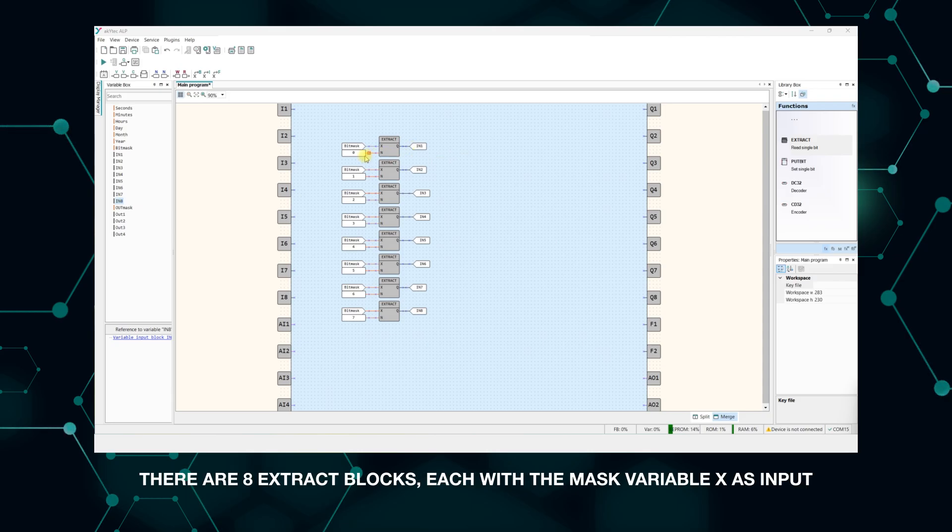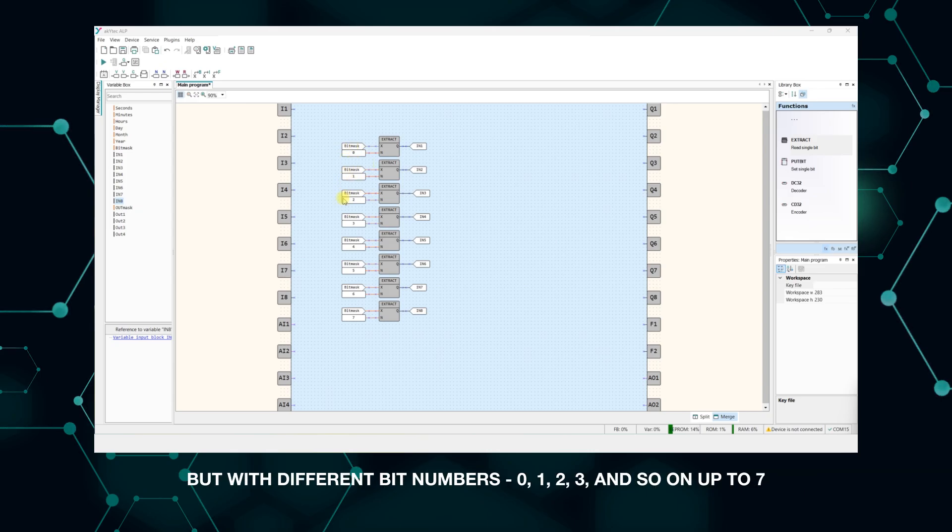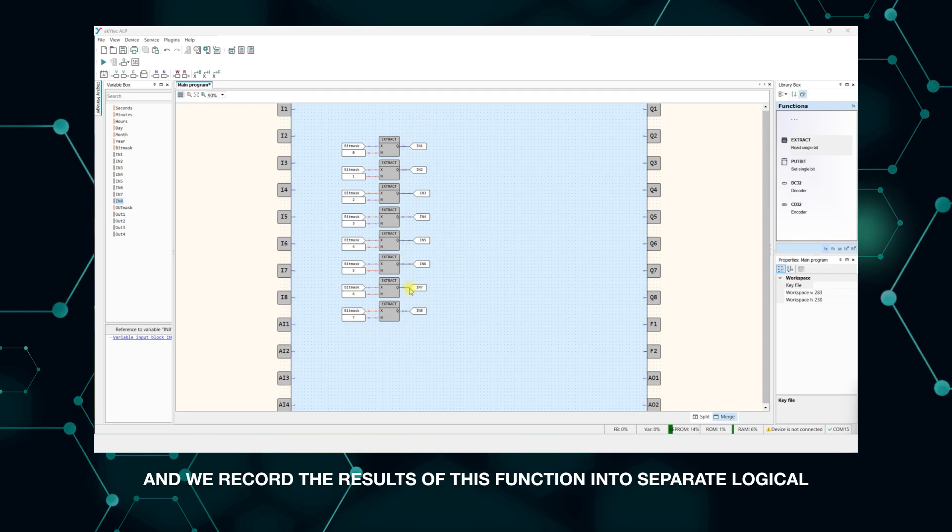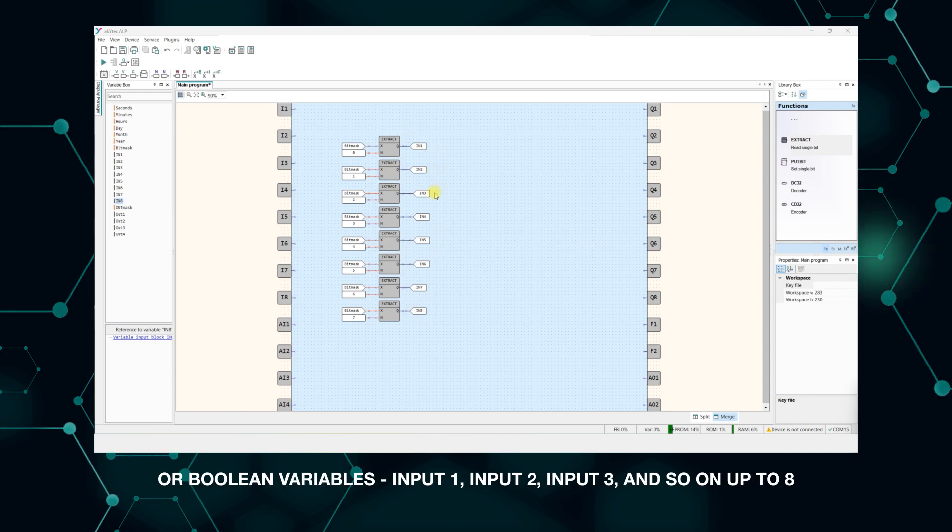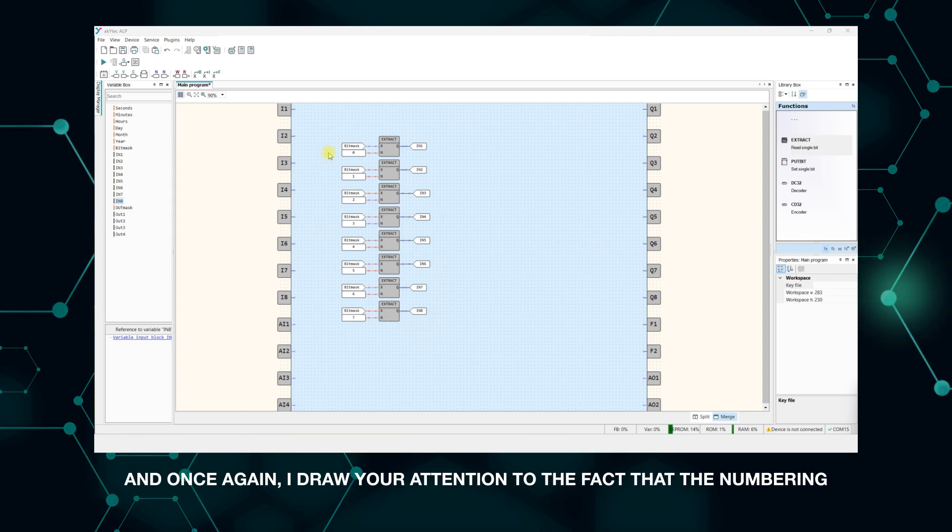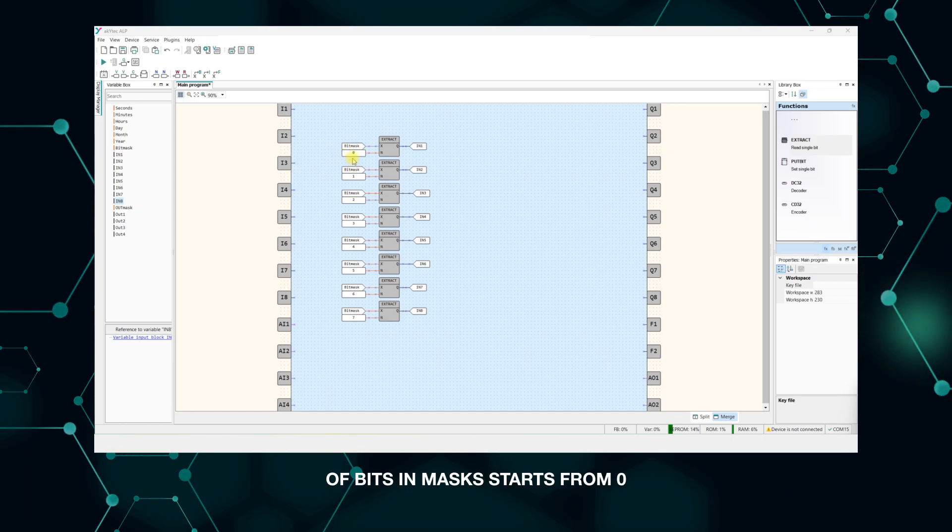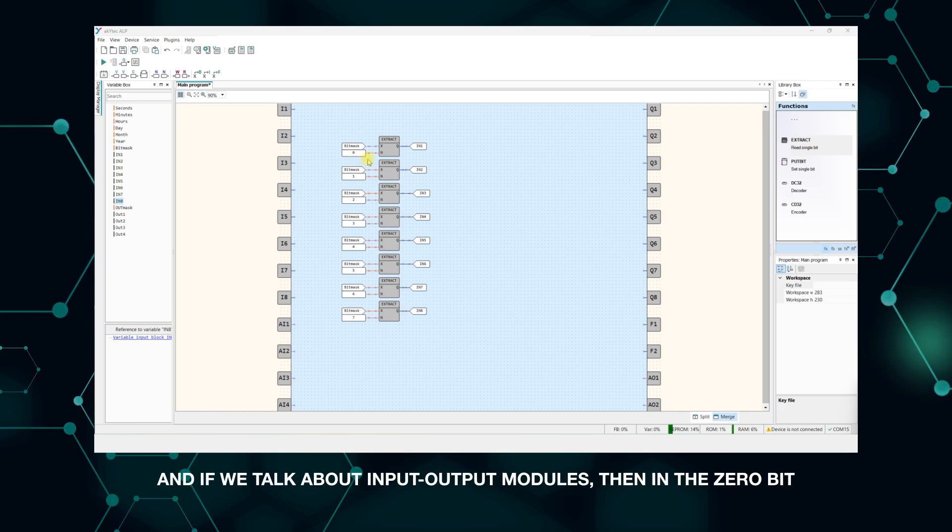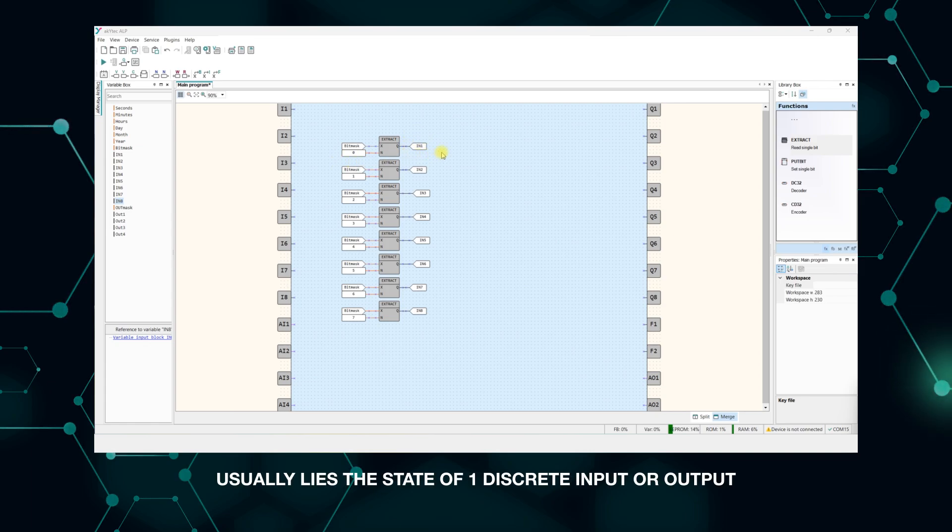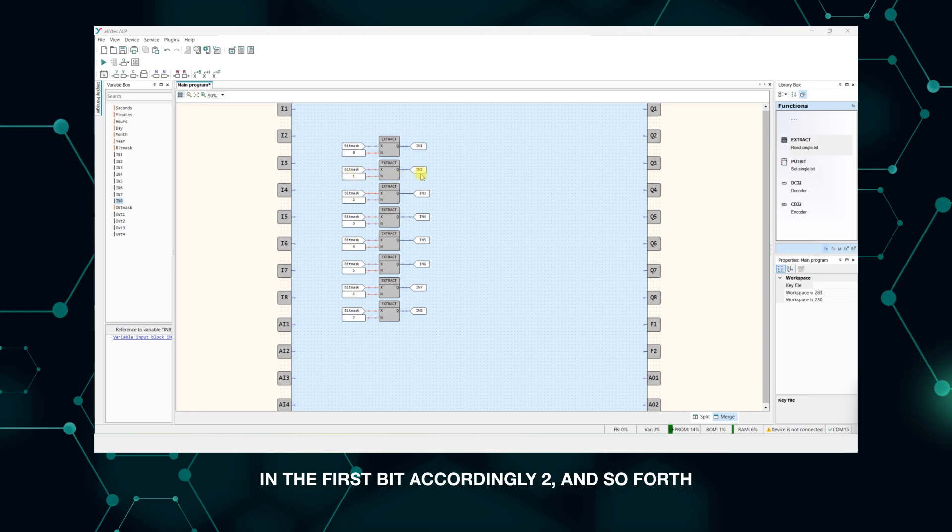There are eight extract blocks, each with the mask variable x as input, but with different bit numbers: 0, 1, 2, 3, and so on up to 7. And we record the results of this function into separate logical or boolean variables: input 1, input 2, input 3, and so on up to 8. And once again, I draw your attention to the fact that the numbering of bits in masks starts from 0, and if we talk about input-output modules, then in the 0 bit usually lies the state of the first discrete input or output; in the first bit, accordingly, 2, and so forth.